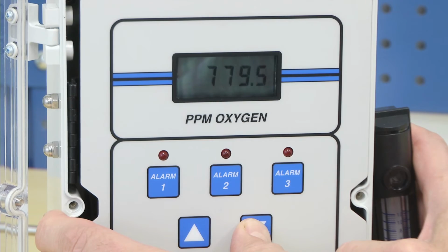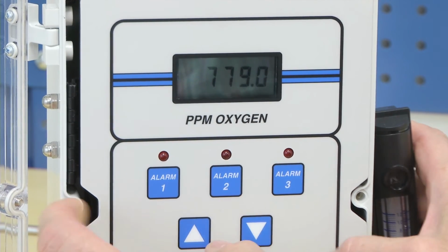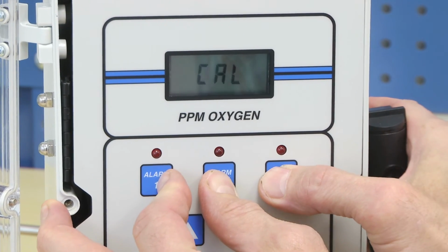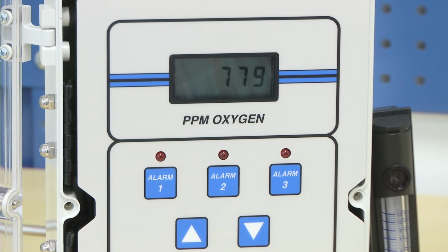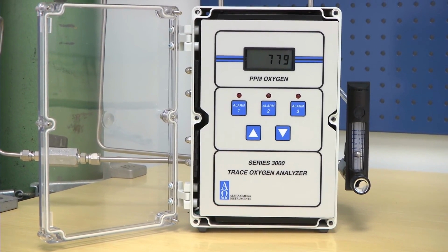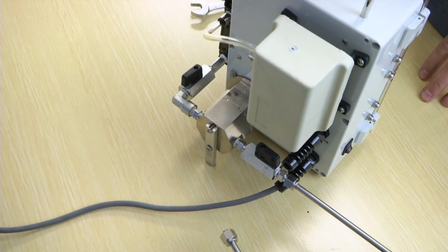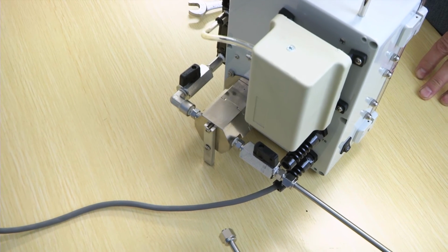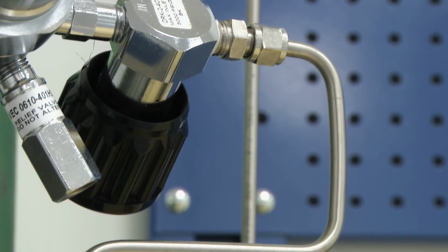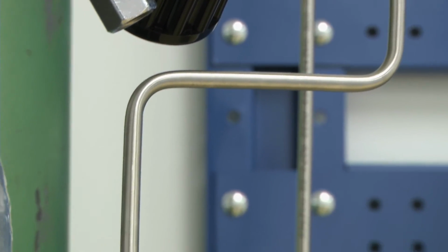Now that the analyzer is reading identical to the calibration gas, simultaneously press alarms 1, 2, and 3 again. The alternating cal message disappears, and your Series 3000 is now fully calibrated. When finished, the manual isolation valves should be closed for instrument storage. In addition, closing the valves also helps to avoid prolonged exposure of the sensor to air.